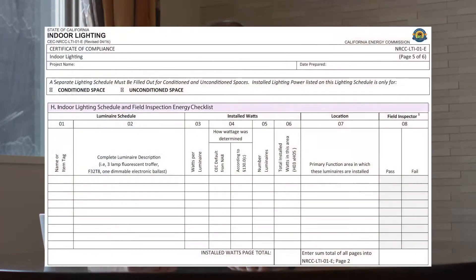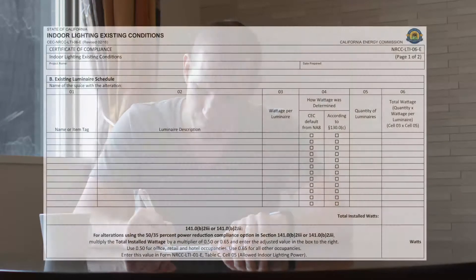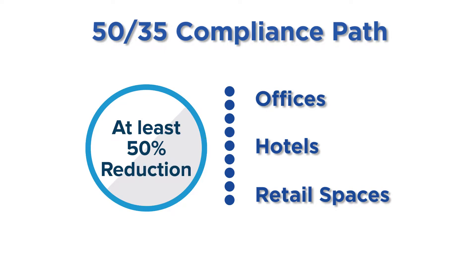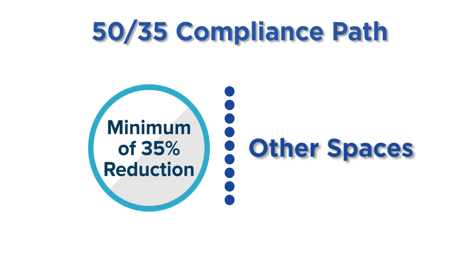Use NRCC-LTI-01 Table H to record the wattage of the replacement luminaires and luminaires with component modifications. Use NRCC-LTI-06 Table B to record the wattage of existing luminaires being altered. Remember, for offices, hotels, and retail spaces, the reduction must be 50%. In all other spaces, at least a 35% reduction is required.